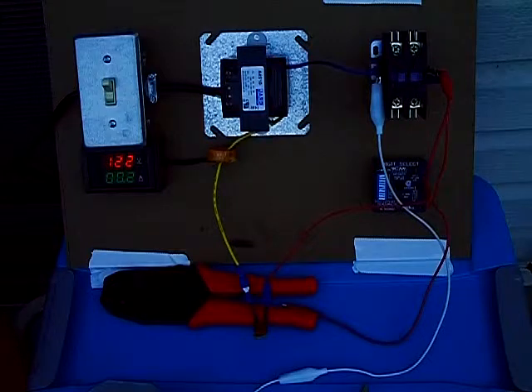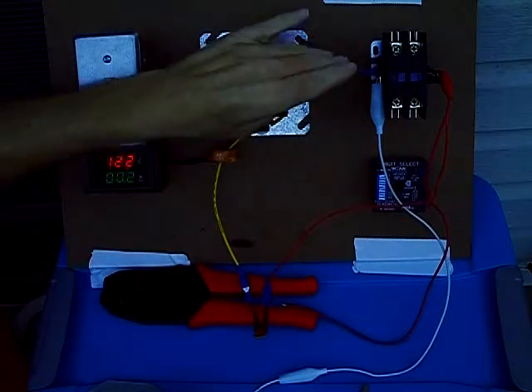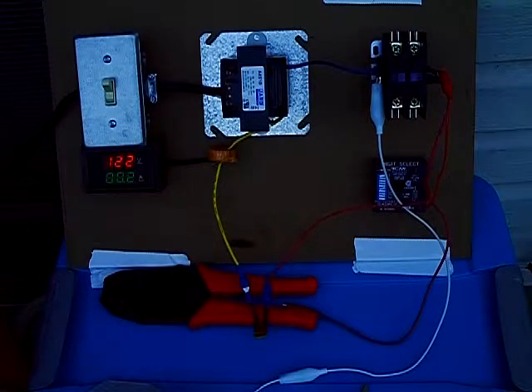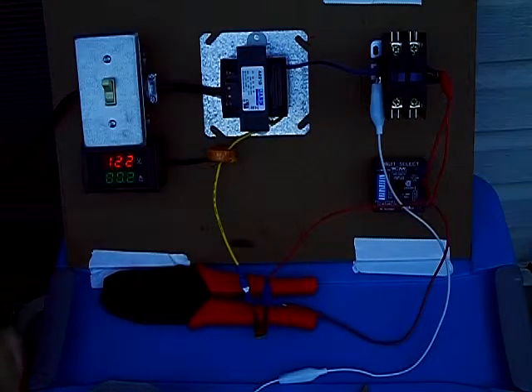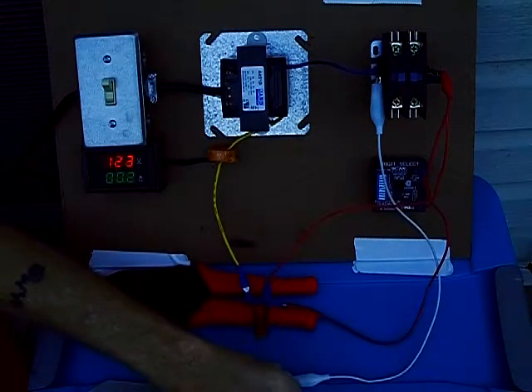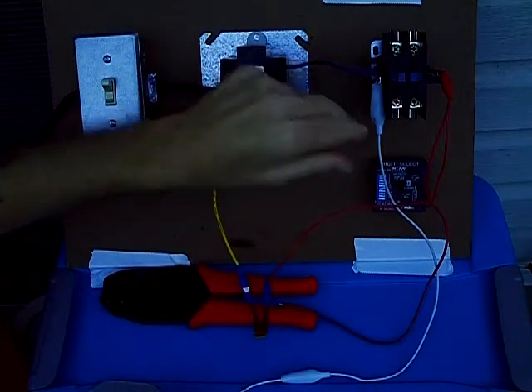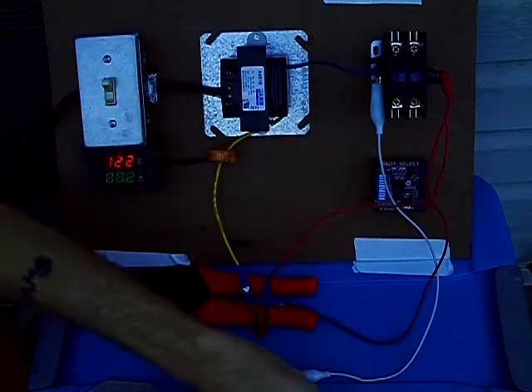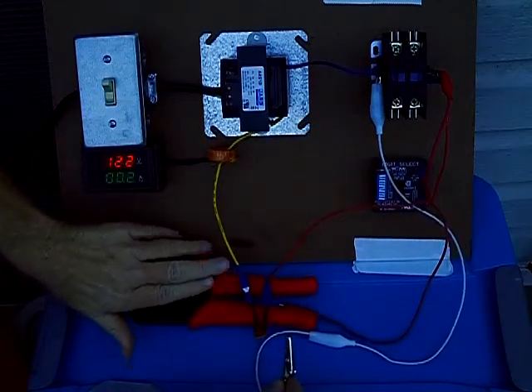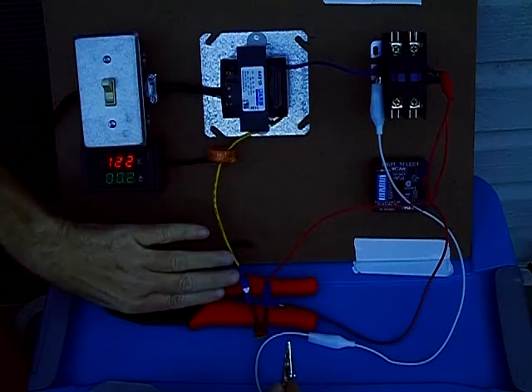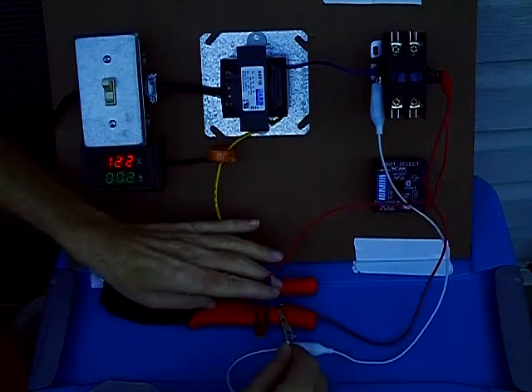I want you to understand, when you create these shorts, you've got to put both sides of the power together, just like you would with a car battery or anything. If you have jumped your car battery before and touched the black and red clamps that you put on your battery, you'll see big sparks happen. That's what you're doing here. You're causing a short. And when you create your short with your jumper, regardless of whether it's a white jumper wire or red or green, it doesn't make any difference. You attach it to this blue or negative side, and you always don't jump it directly to the transformer, the yellow wire coming out. It has to be on the output of your protection.